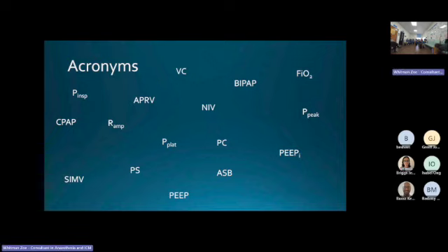If they're breathing through a tube, it doesn't seem to matter. If they're breathing spontaneously through a non-invasive mask and they're finding that difficult to tolerate, the simplest thing that often makes a big difference is to increase the ramp speed, or whatever the new one's called. It's in the settings. It's one of the little blue circles that you swivel on the Drägers. If you increase it to somewhere between half a second and a second, suddenly they go, oh, that's easier.